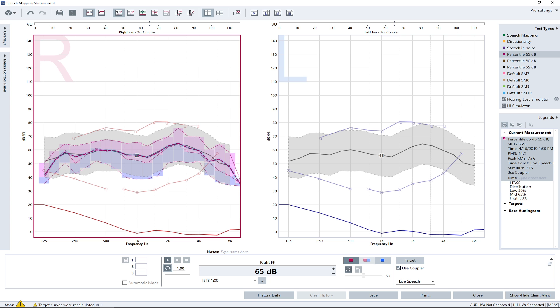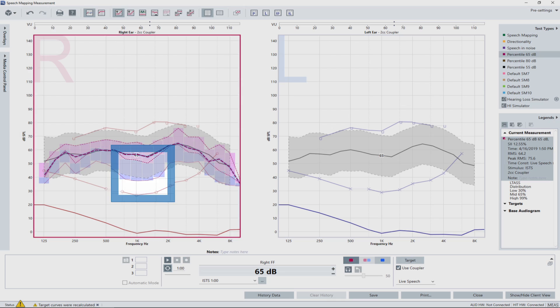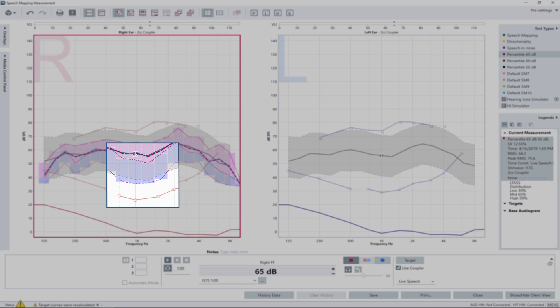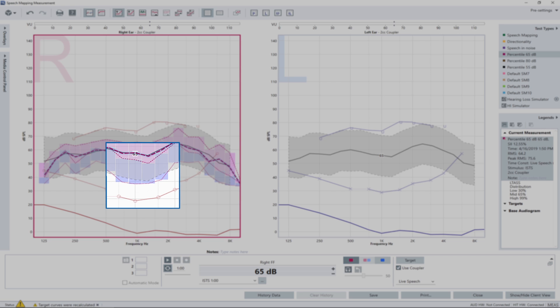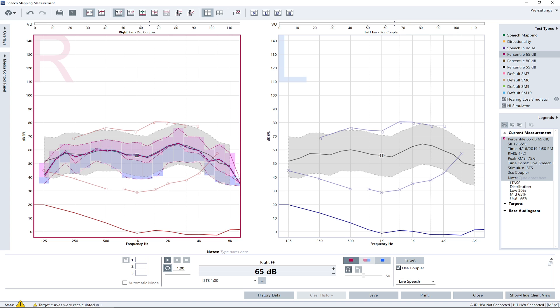Once the LTAS curve is matched, check that the bottom line of the blue bar at 1000 Hz is above the hearing threshold level. As the blue bar represents the soft portion of speech, it will indicate that soft sounds are still audible with speech input on average loudness level. If this is not the case, consider increasing the gain for soft sounds. Now the hearing aid has been fitted for a medium sound level input and should already match loud sounds targets due to its pre-configured compression setting from the first fit.